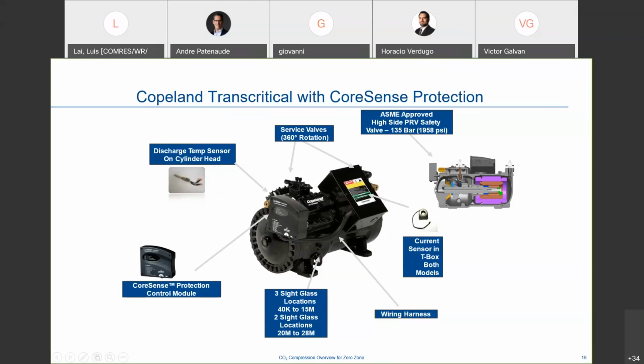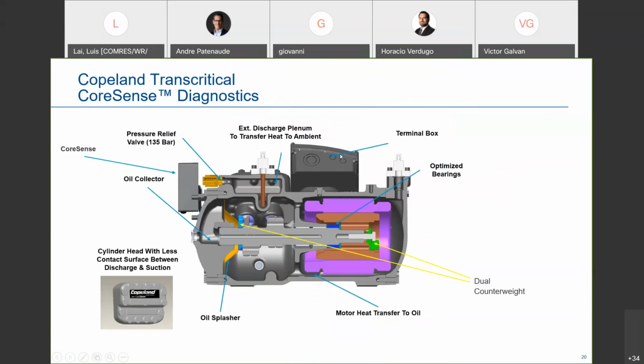And because of that, we can have a sight glass on the right side, the left side, and even one up here. And I'll show you on the next slide the value of having a sight glass that high up on the compressor. We have a CoreSense module, and I'll talk a little bit about that. There's a current sensing toroid inside the electrical box. And I mentioned our electrical box is made of metal, rather than this one here. This image shows a plastic rounded version, which is a European image. So here's the terminal box. If I walk around this compressor, starting from the top right here, we've got the discharge valve. I said 135 bar. And you'll notice on the next slide, I'm saying that originally this compressor also had a suction pressure relief of 90 bar.